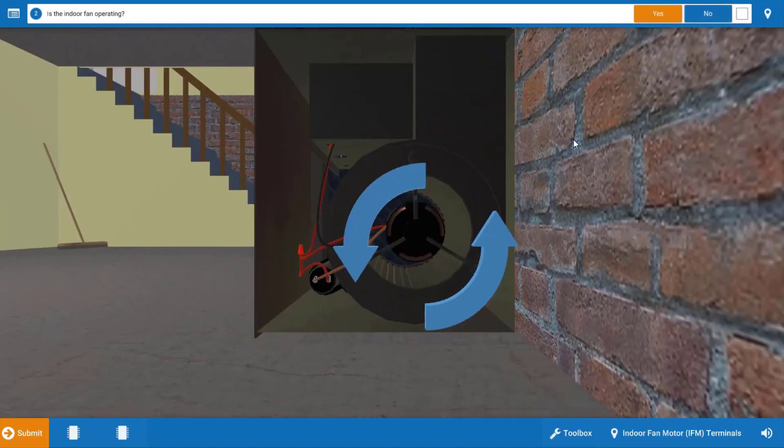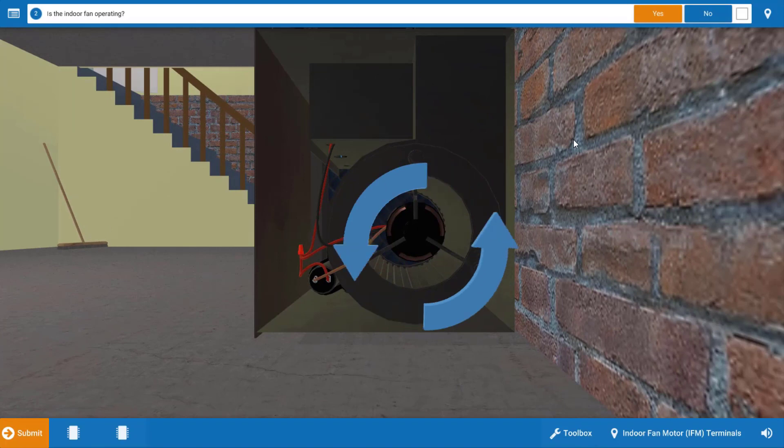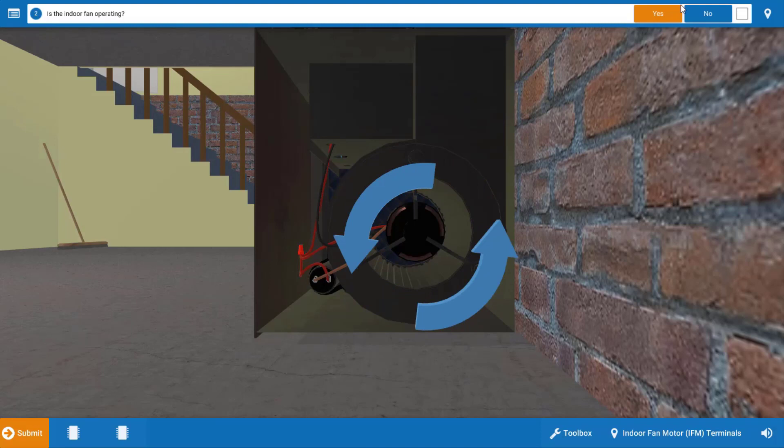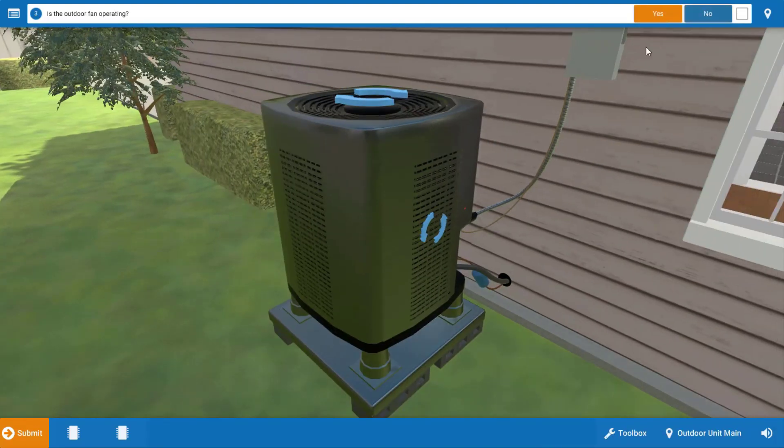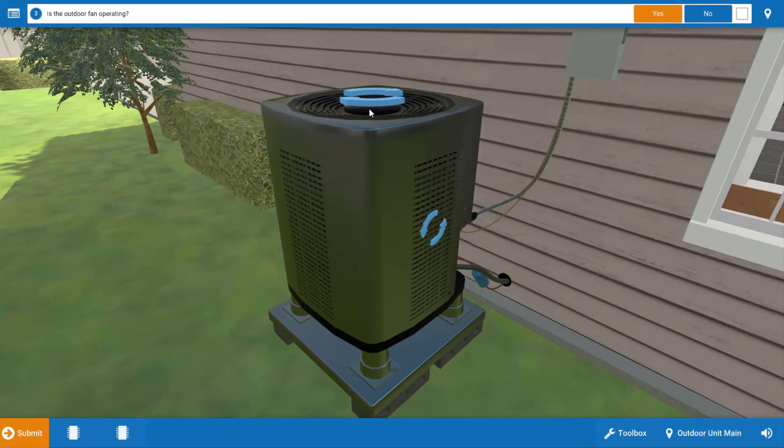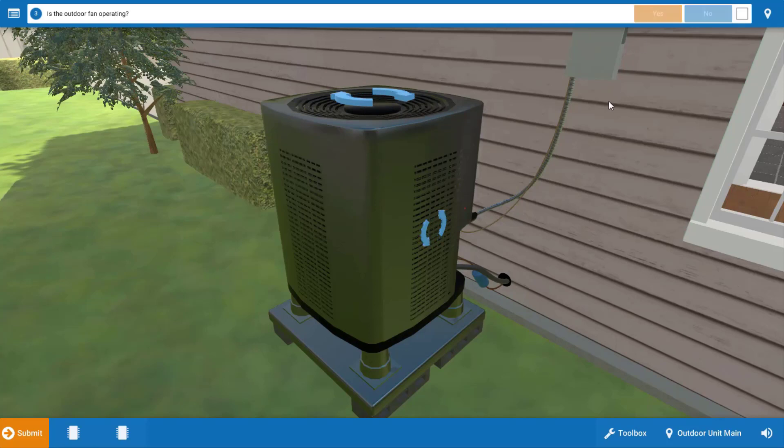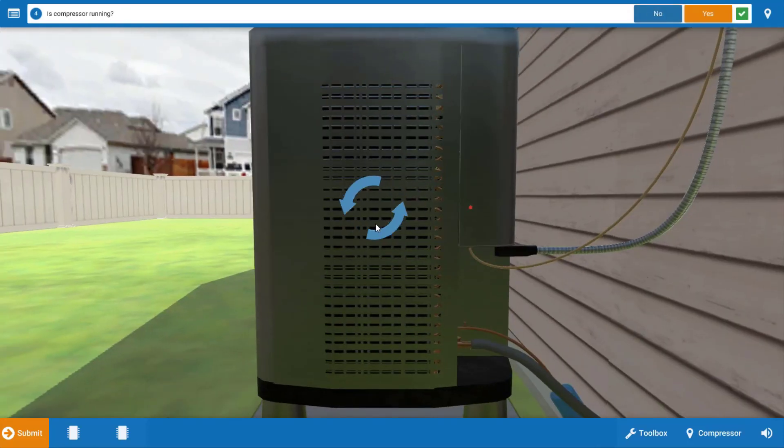Now we want to assess which electrical loads are running and we can see here that the indoor fan is in fact running as evidenced by the spinning blue arrows. We're going to click yes and we go to the outdoor unit and we see that the outdoor fan is in fact operating, or the condenser fan motor. We're going to click yes and it appears that our compressor is also operating.